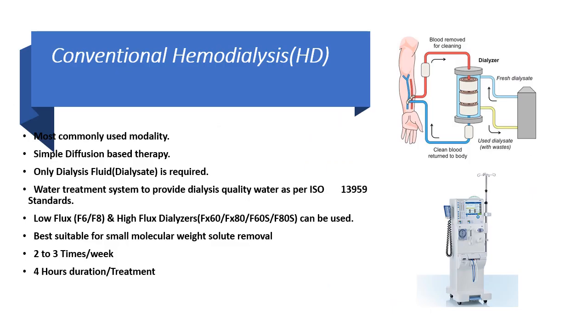Our first modality is conventional haemodialysis. I won't go into much detail because the topic is well familiar to all. Conventional haemodialysis is the most commonly used diffusion-based modality. Only dialysis fluid is required to facilitate diffusion during the therapy. To prepare the dialysis fluid, the machine requires an RO water treatment system along with Part A and Part B concentrates.